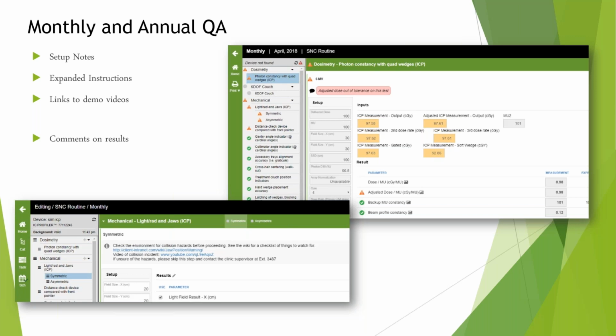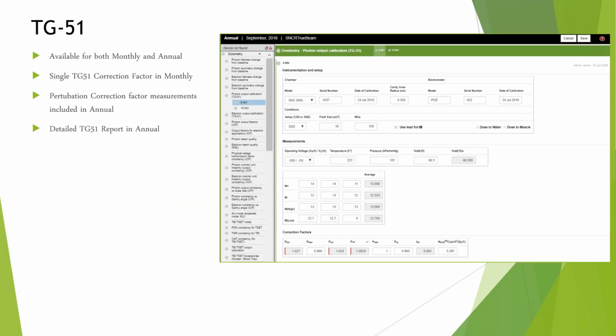TG51 is included in the system in both the monthly and annual modules. In the monthly module, there's a single correction factor. Then within the annual module, you have a space to enter all perturbation correction factor measurements. And with the click of the mouse, you get a detailed TG51 report in the annual.